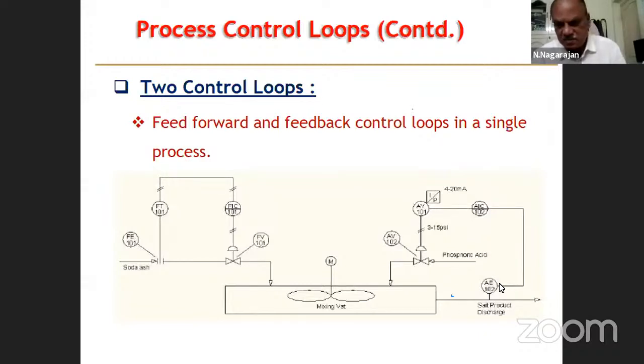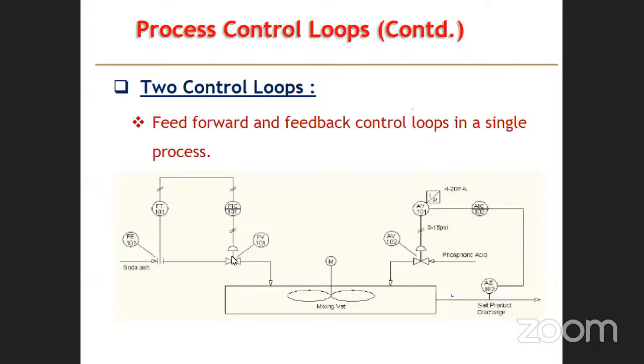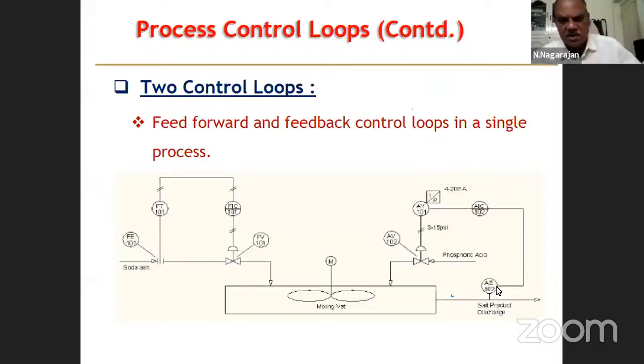Okay. Here it is feedback control. Here the soda ash is being added, which is the main raw material coming into the process. So the soda ash flow rate is measured before the control element. You simply remember, if the measurement is before the control element, it is feed forward. If the measurement is after the control valve, that is feedback control. According to the flow rate measured upstream of the control valve, the signal is going to the flow indicating controller, where you have the set point, and that control action is decided, which will operate the valve. So you have a feed forward controller and a feedback controller in the same process. These combinations are possible.